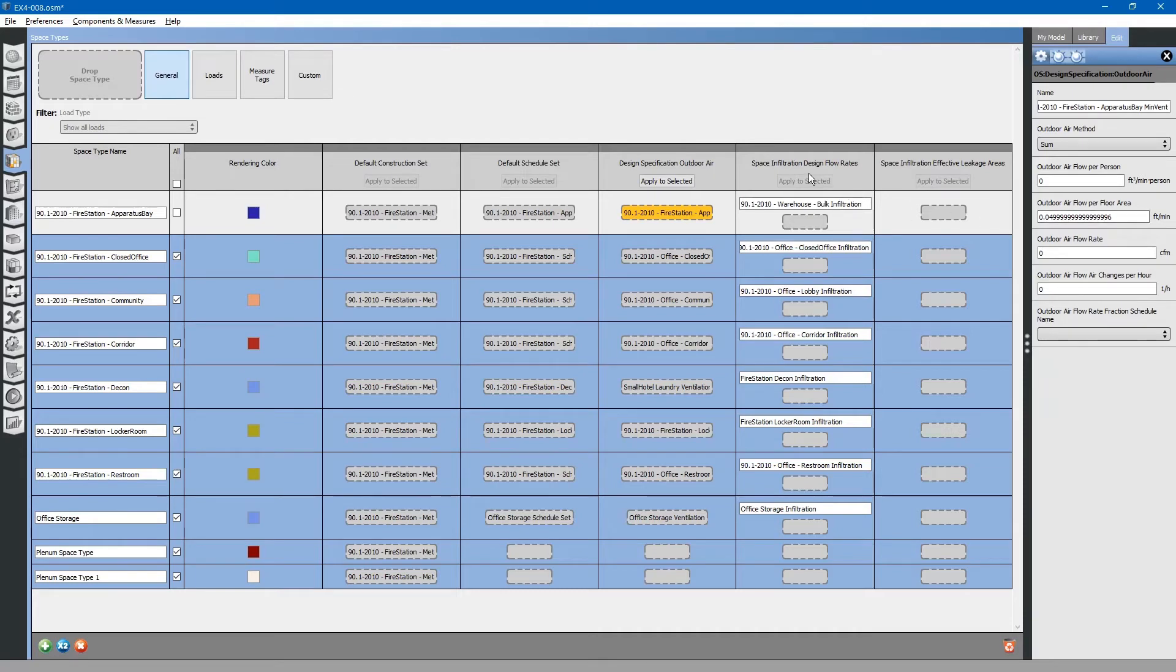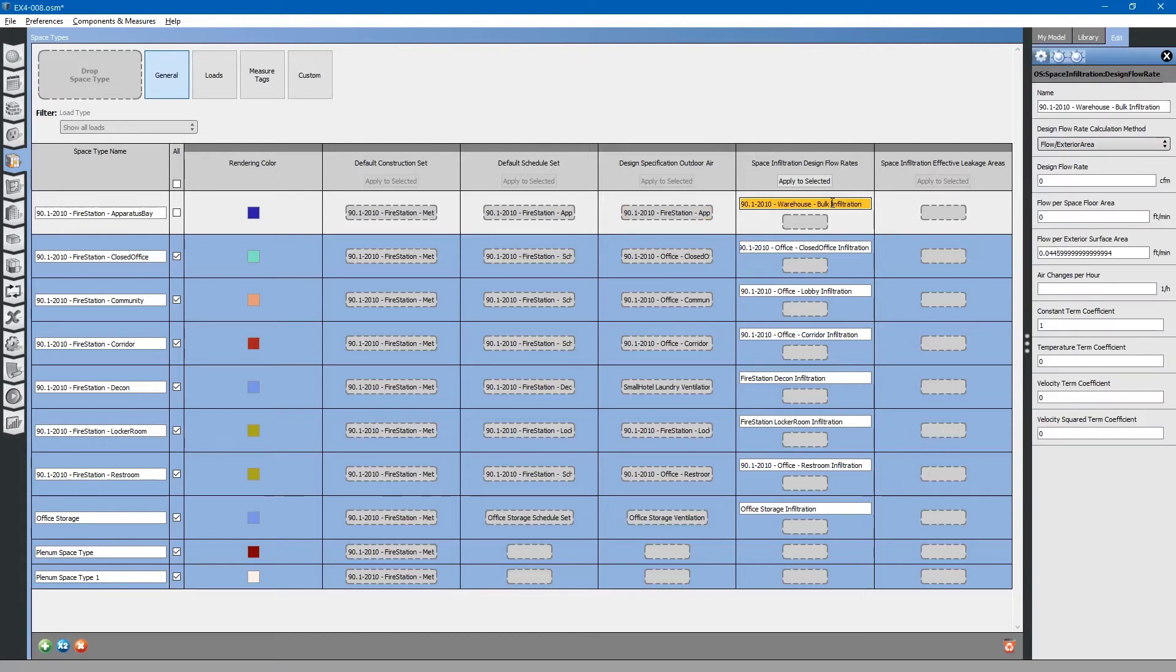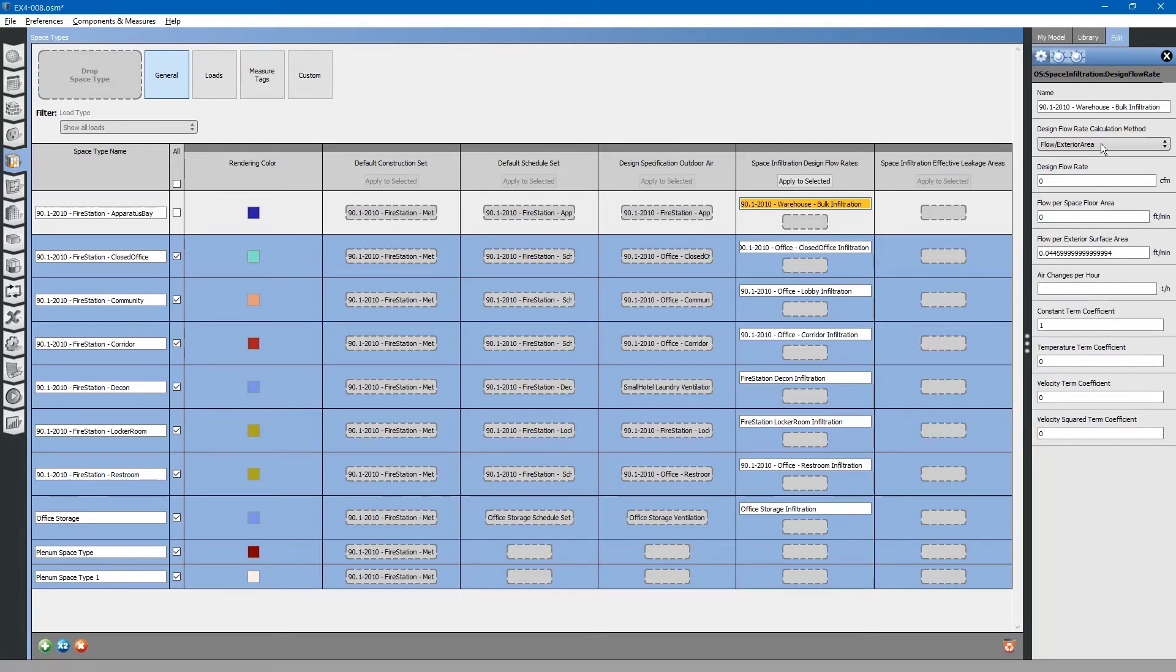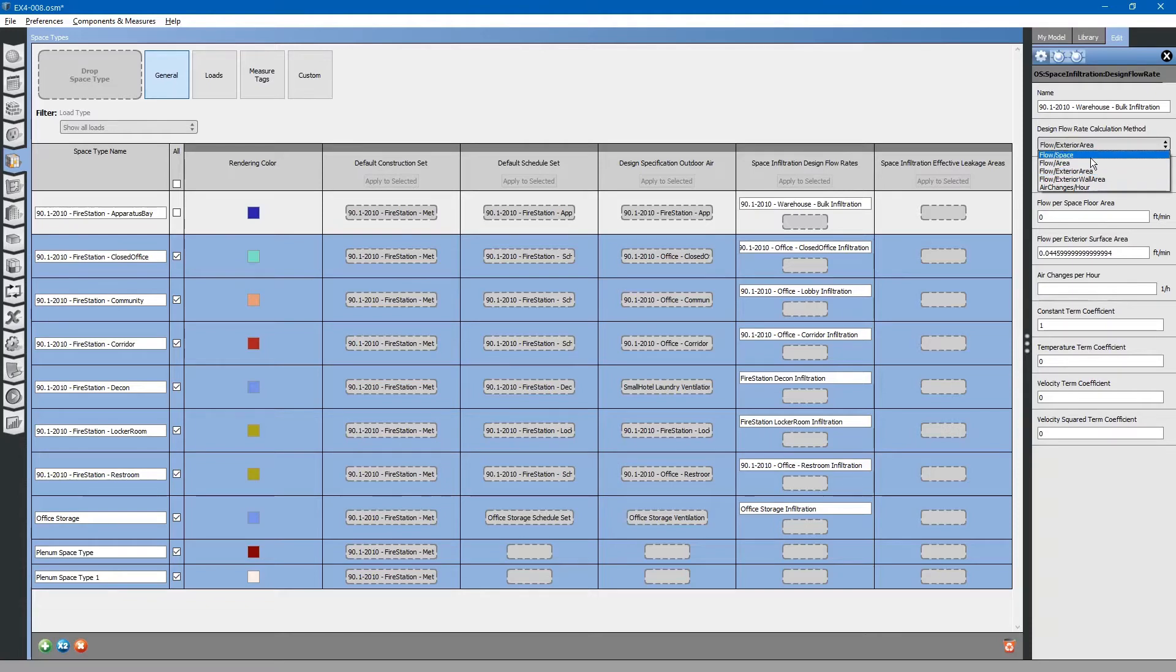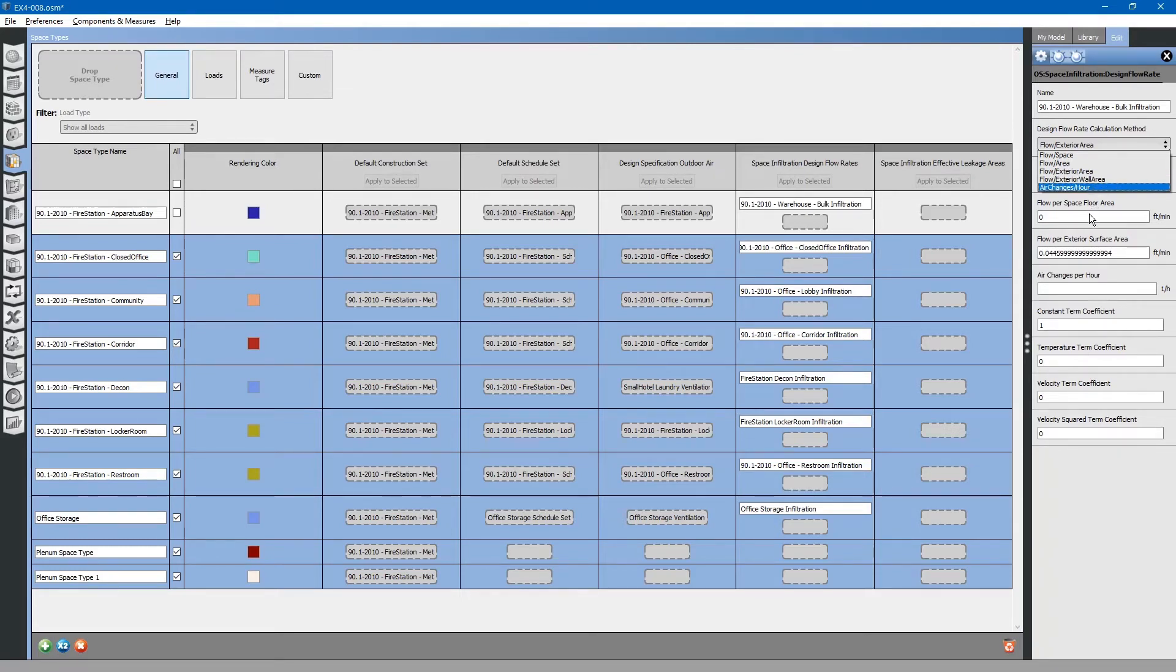On this column, you will see space infiltration design flow rates. The space infiltration design flow rates are also specified. You can change the flow rates based on floor area, based on total space, based on exterior surface area of the roof and walls, or just exterior wall areas. You can select air changes per hour.